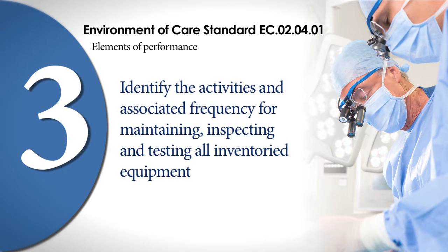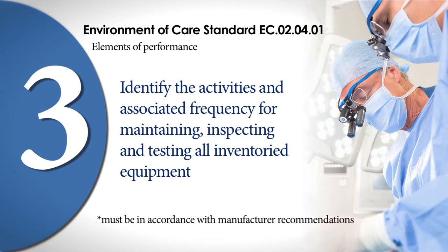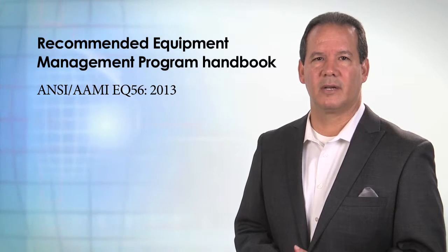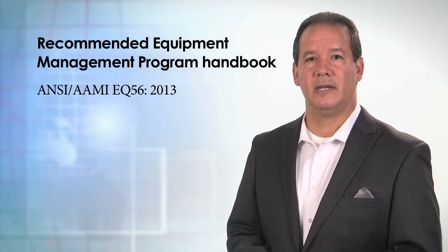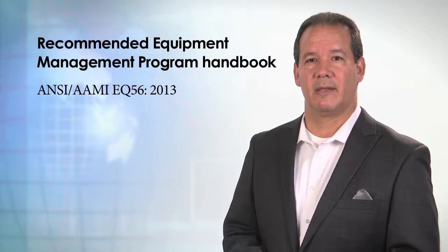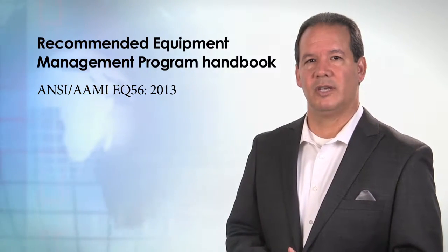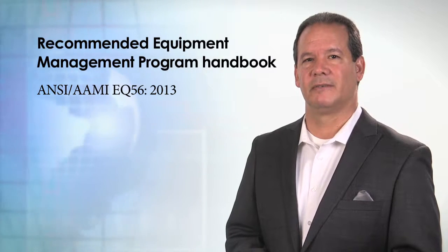Third, identify in writing the activities and associated frequency for maintaining, inspecting, and testing all medical equipment listed on the inventory. These activities and associated frequencies must be in accordance with the manufacturer's recommendations or with strategies of alternative equipment maintenance, or AEM, programs based on the manufacturer's recommendations. The strategies of an AEM program must not reduce the safety of equipment and must be based on accepted standards of practice. An example of standards for a medical equipment program can be found in the Recommended Equipment Management Program Handbook, published by the American National Standards Institute and the Association for the Advancement of Medical Instrumentation.